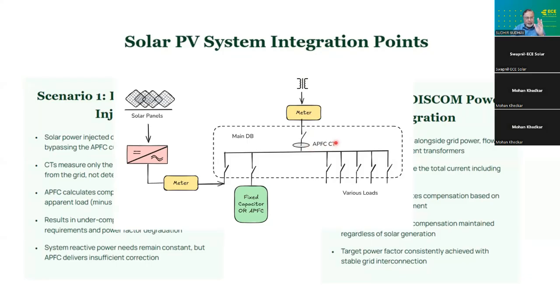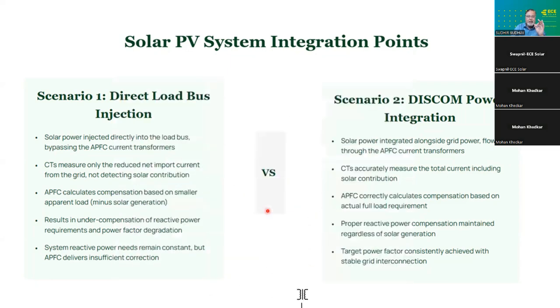But what happens? My CTs are here. They cannot sense the total X component. What the CTs are sensing is X minus Y, and accordingly they will fire the capacitors. So that is precisely why the capacitor or APFC starts misbehaving.